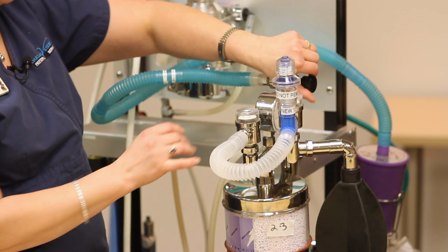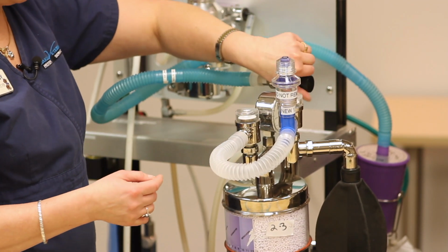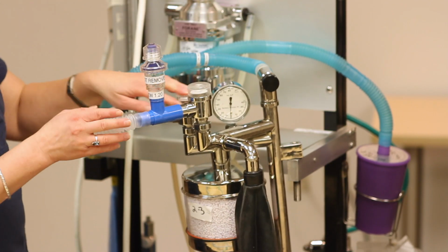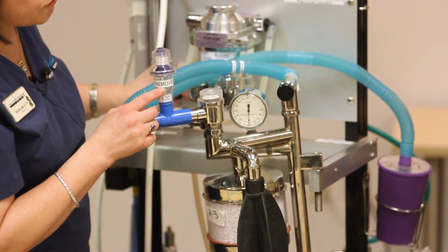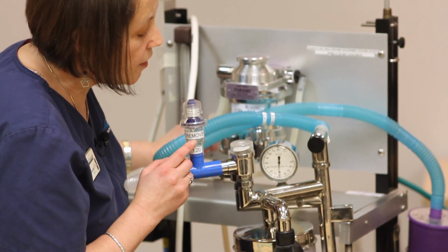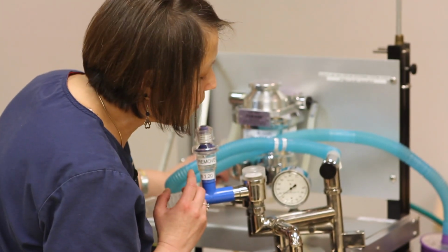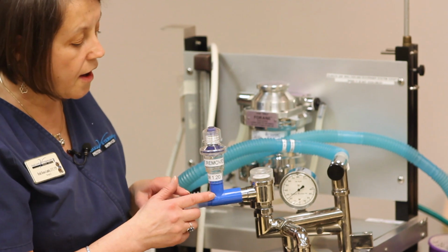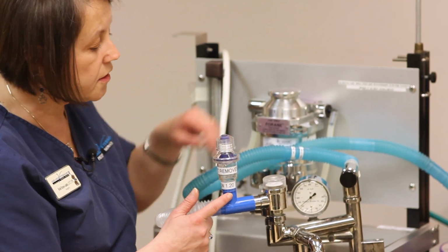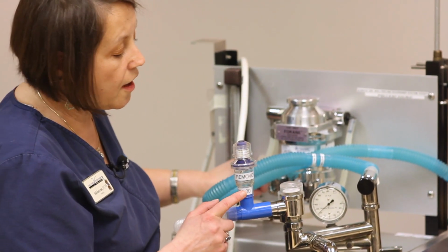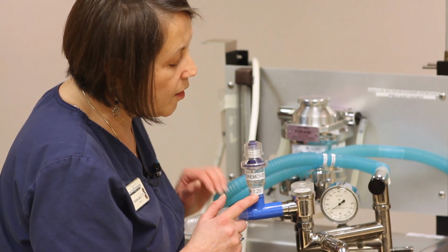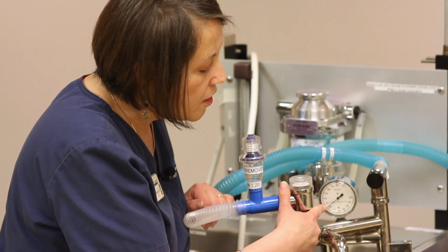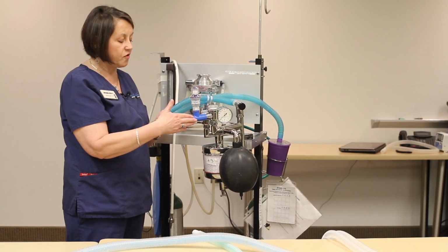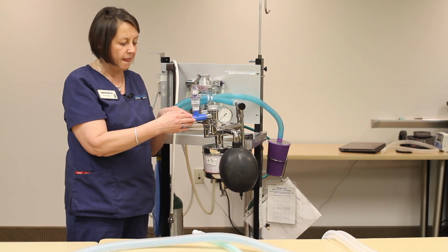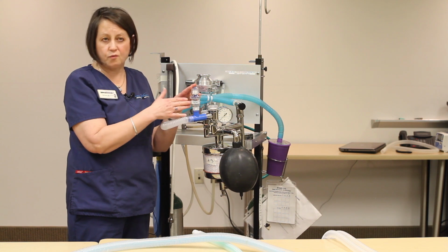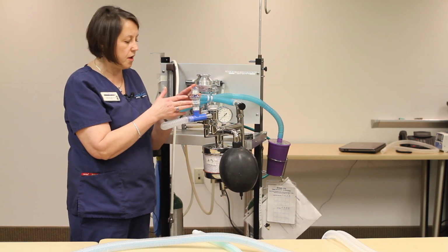So what you're going to do is shut your pop off, and then you're going to pressurize the circuit. And with this safety feature in place, we really shouldn't be able to pressurize this circuit for more than about 20 centimeters of water. And here you have that safety feature activated, where even if I push the oxygen flush valve, I'm not able to get that to go more than 20 centimeters of water. So these always belong on the expiratory side of the machine, and these should never be removed. These will work even with a ventilator in use.